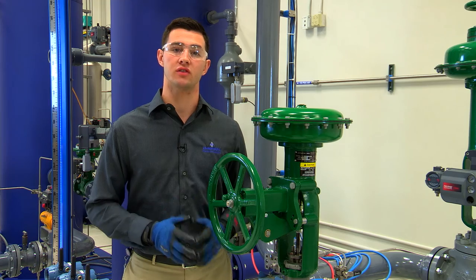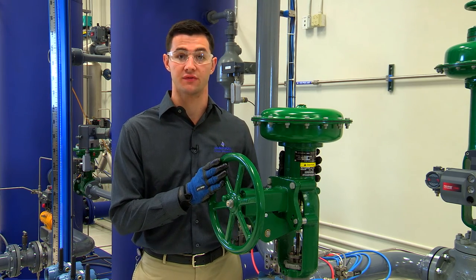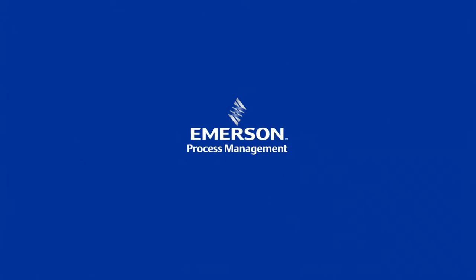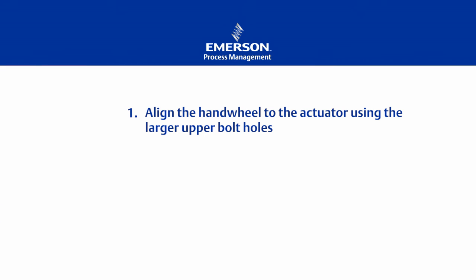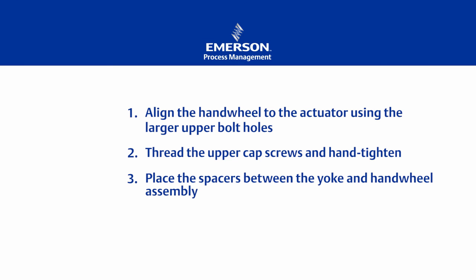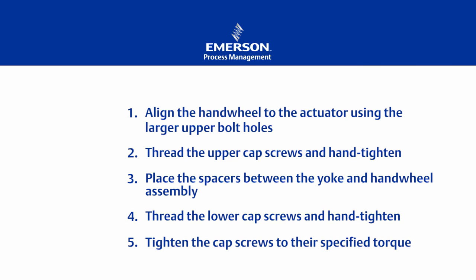We've just learned how to install a side mounted hand wheel to a Fisher 657 size 40i actuator. So let's review the steps we took. First, align the hand wheel to the actuator using the larger upper bolt holes. Second, thread the upper cap screws and hand tighten. Third, place the spacers between the yoke and handwheel assembly. Fourth, thread the lower cap screws and hand tighten. Finally, tighten the cap screws to their specified torques.